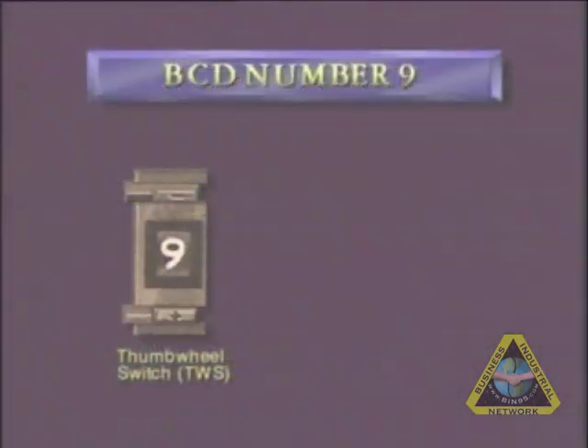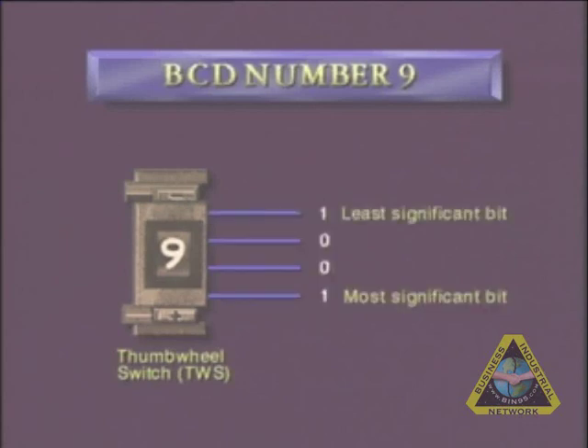When we select numbers in thumb wheel switches, the switch, in actuality, sends to the input module of a PLC four lines representing each number, each line being on or off, to signify the one or zero condition according to the number selected in the thumb wheel switch.